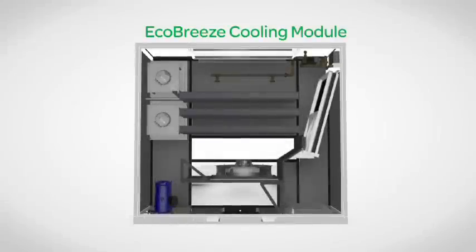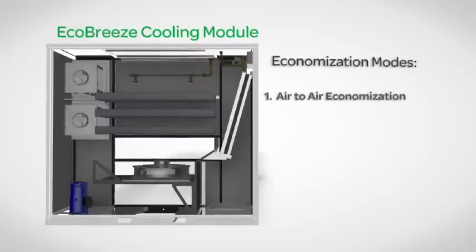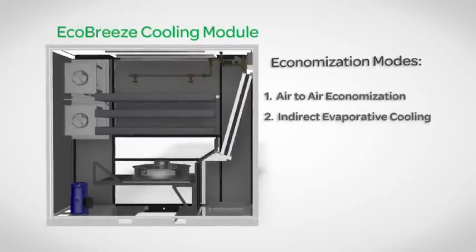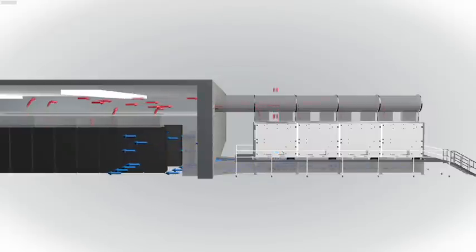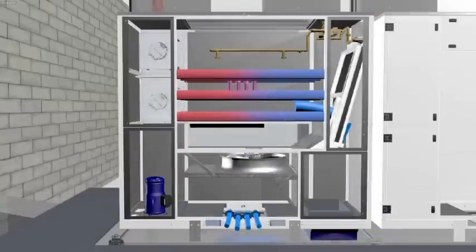Unlike other free cooling systems, EcoBreeze offers two separate methods of economization, not just one. The first is air-to-air economization. Air-to-air economization works by taking two airstreams, the outdoor air that's cooler, and the indoor air that's heated from the IT equipment, and doing a heat exchange between the two without ever mixing them. And the heat exchanger is designed using specific materials designed to transfer that heat from one airstream to another.